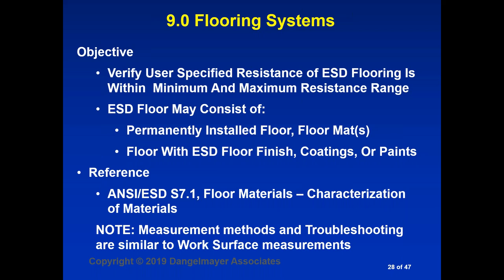And we're not going to go into these measurements in detail because they're exactly the same as the work surface measurements. You have a meter, you have one electrode, you connect the meter to ground, you connect the electrode to the meter, and then you measure from the floor to your AC ground. In fact, when you're making measurements in your work area, you may find it very convenient to set up your meter, make a measurement on the work surface, and then transfer the electrode to the floor and make a flooring measurement in the same area. You don't have to change your setup. You just have to change the location of your measurement electrode.